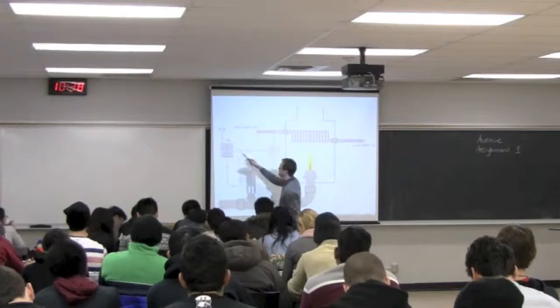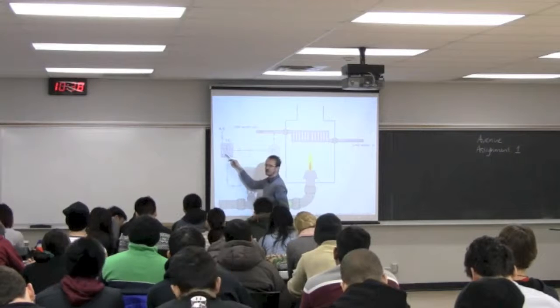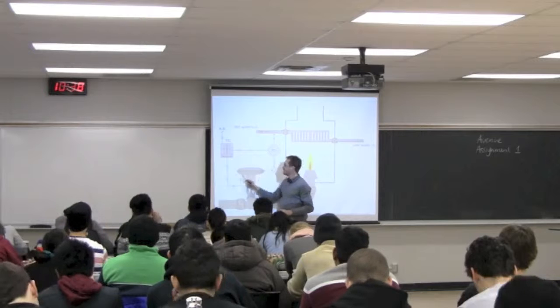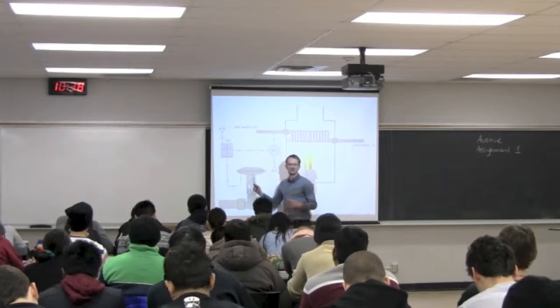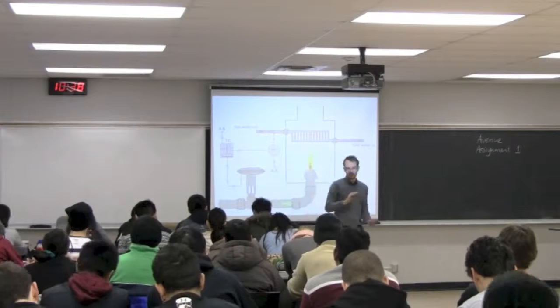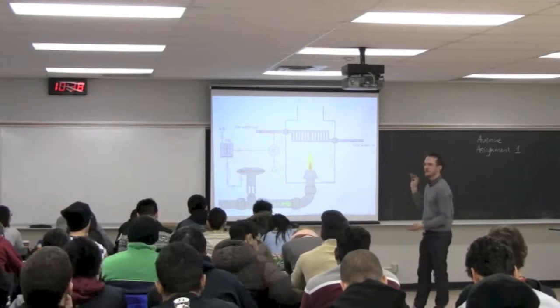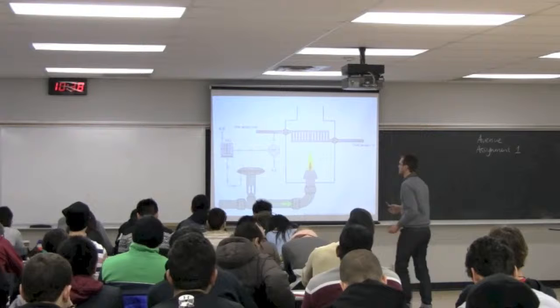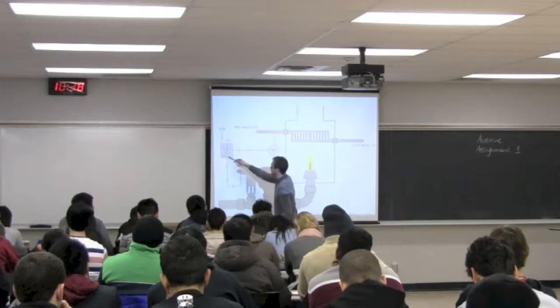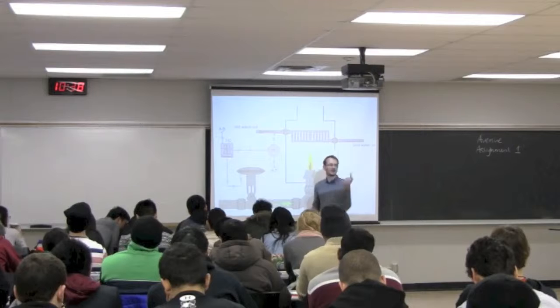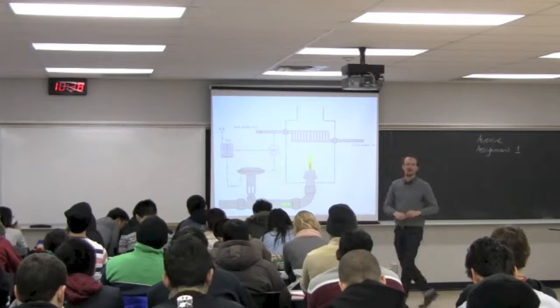And then this control system is doing a calculation and sending a signal to the valve, telling the valve to open and close by a certain percentage. A 0% signal is fully closed, and a 100% signal tells the valve to be fully open. Again, this is transmitted through a pressure signal to this valve, and that valve will automatically open and close depending on the signal coming in.